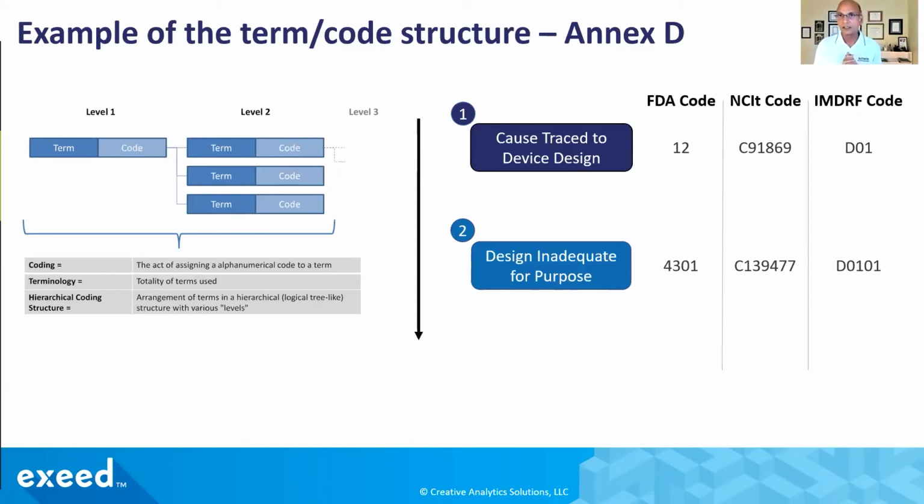I heard from one of you that you are reporting based on these codes. Should the same codes and terms be reflected in our risk management files, so that the probability of harm and the probability of failure modes that we calculate are all aligned with what we are learning from the field? If we are using different terminologies, most likely we are not looking at the complete data. That's the point I want to communicate.